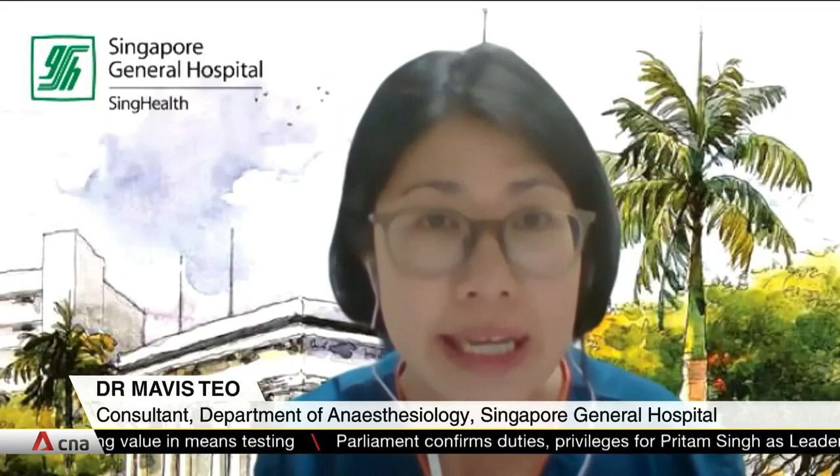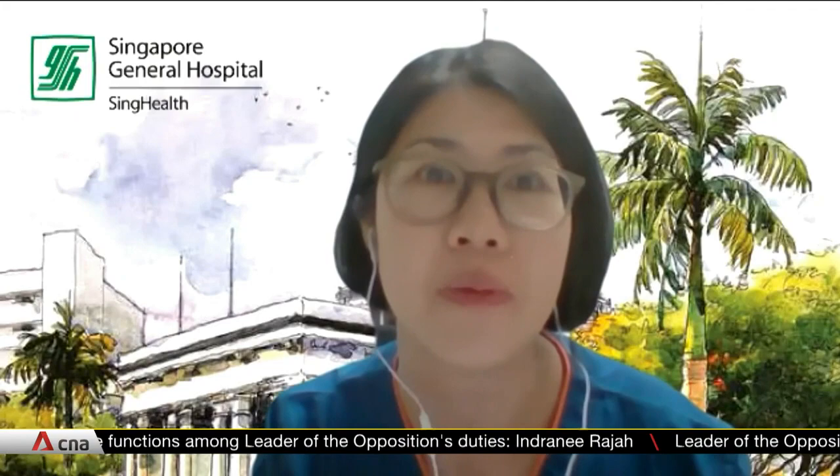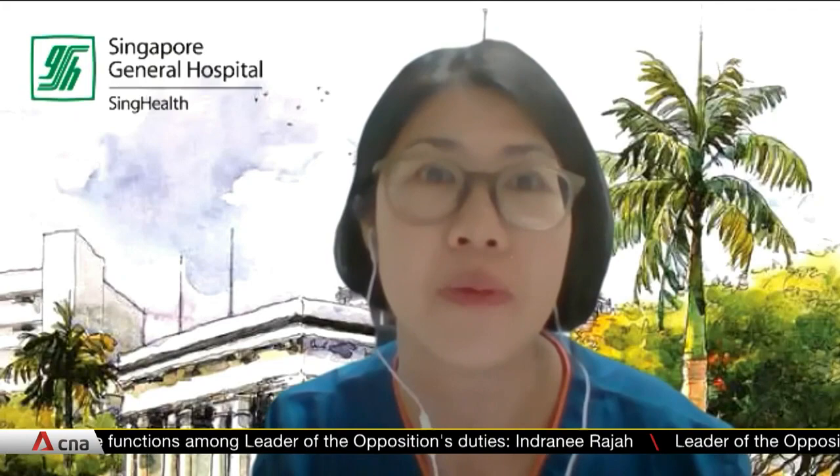With this anteroom in place, which is negatively pressured, clean air can only enter from the corridor into the patient's room. However, potentially contaminated air from the patient's room will not be allowed to escape, and therefore it will protect our healthcare workers who are out in the corridor.